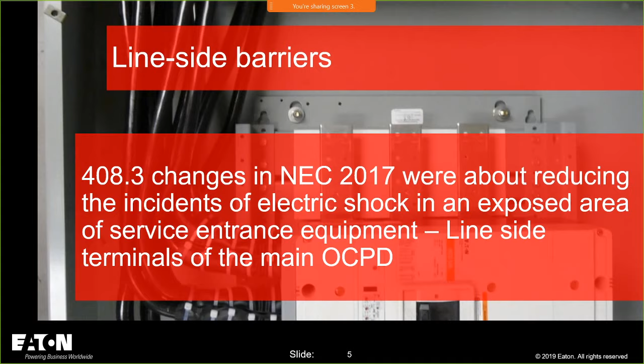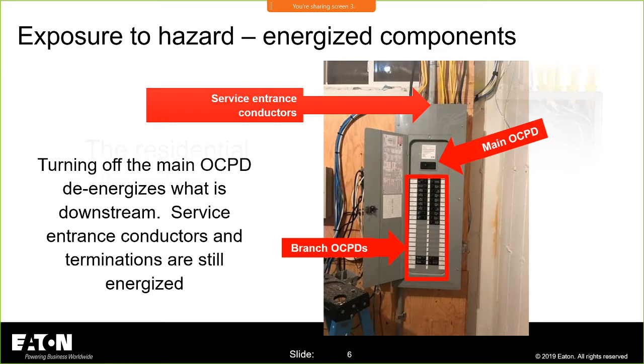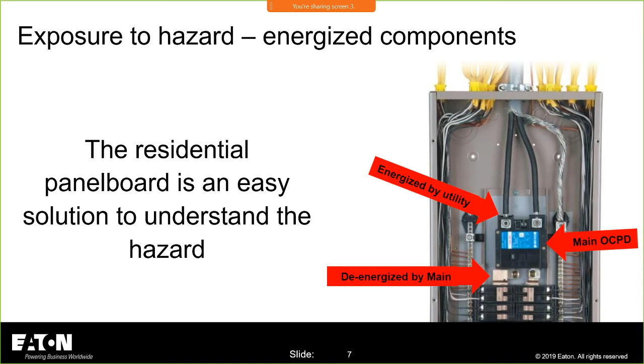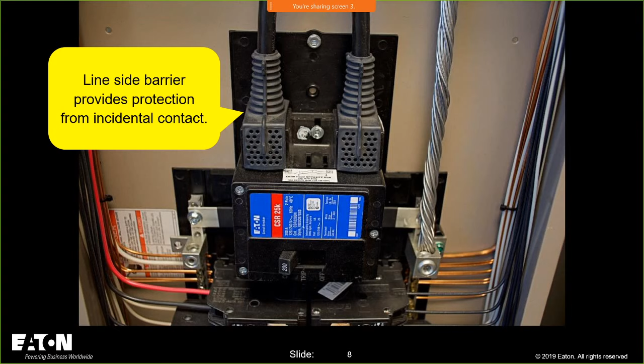For those on the phone who may not know, that service entrance in this case, that main overcurrent protective device is the one up at the top, and all of your branch and feeder devices down and below that. Turning off that breaker does not mean that I have de-energized the line side lugs, because those are energized from the utility, and the only way to turn those off is to call the utility and have them turn that power off for you.